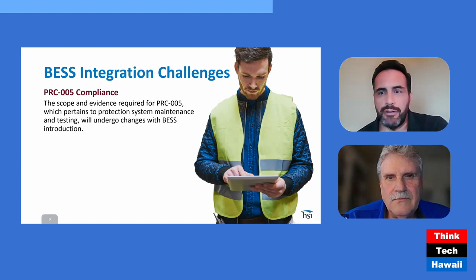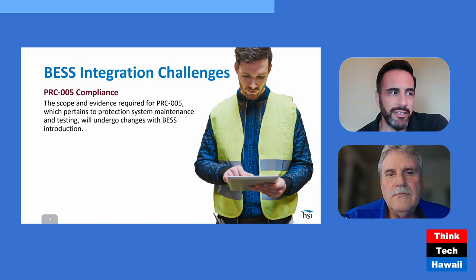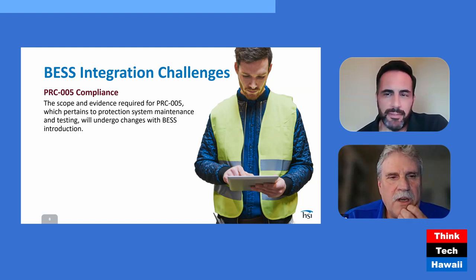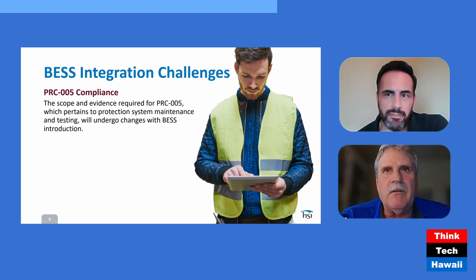Those test records need to be at the correct date, within the correct window, and everything has to be examined and tested prior to commissioning usually. Starting with your commissioning date, the commissioning paperwork will once again be the start of that timing window for when you have to test and maintain your relays, your PTs and CTs, and communications systems within your protected devices. But from then on, it tends to be work orders that you use as proof—when the next window comes up and you need to test and maintain them again, those tend to be work orders, and that's fine.